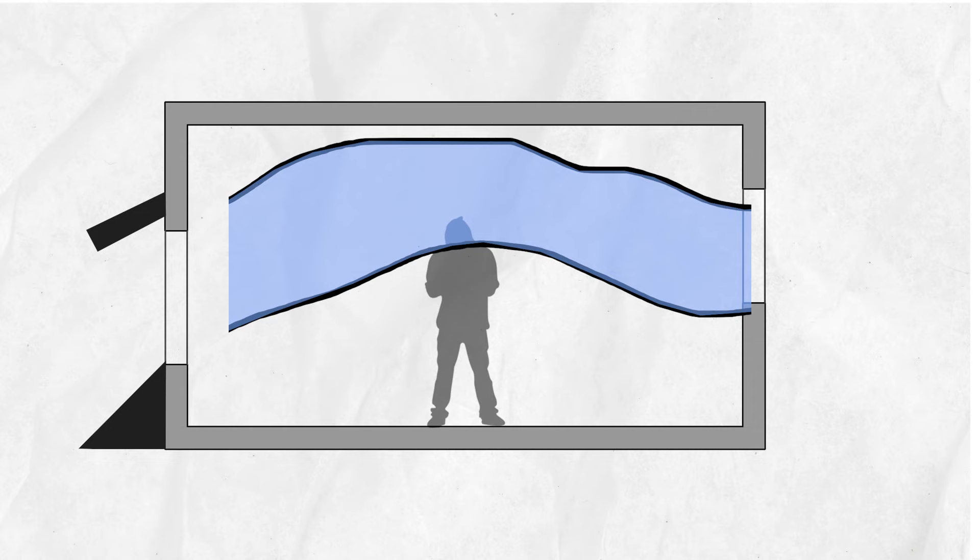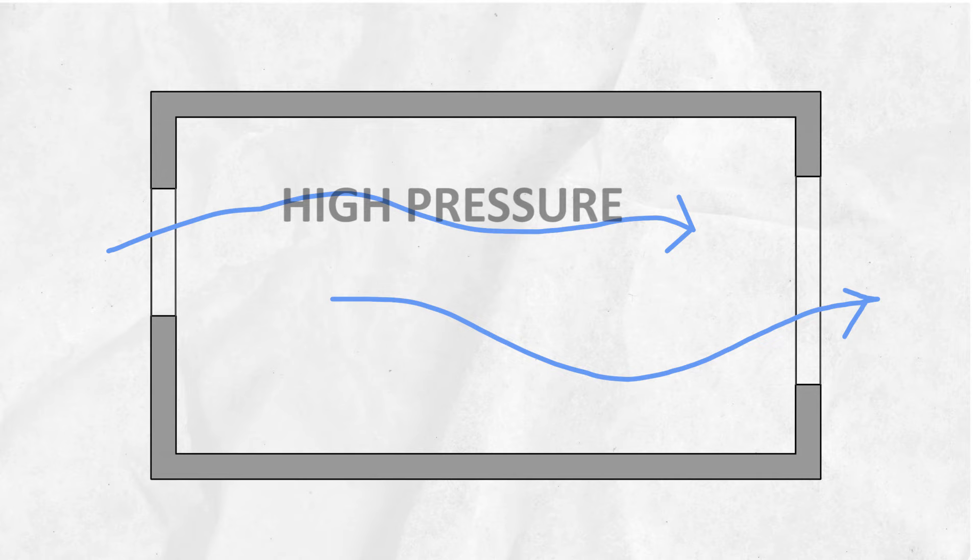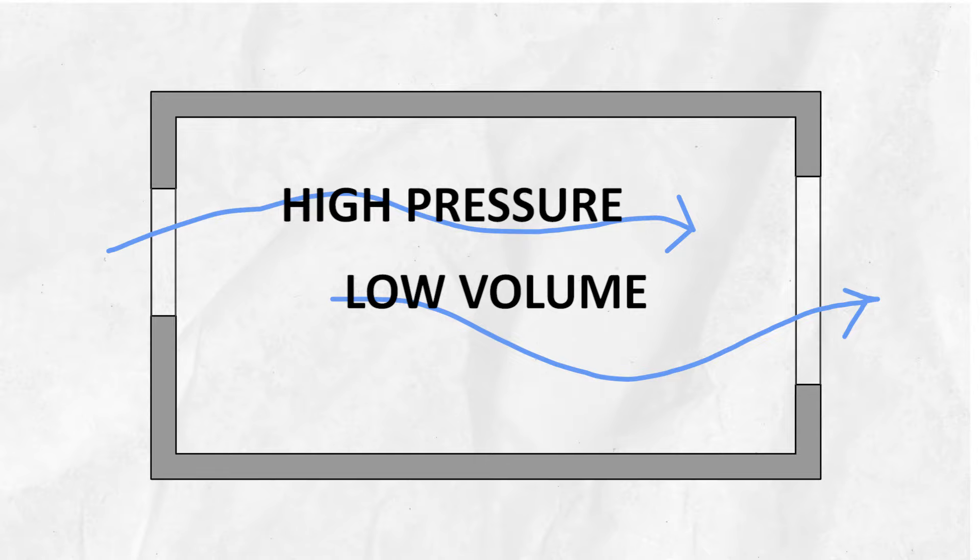Wind direction is mostly guided by the solid area around the building. The largest air velocity will be obtained through a small inlet opening with a large outlet. Such an arrangement may be useful if the air stream is to be directed at a given part of the room.